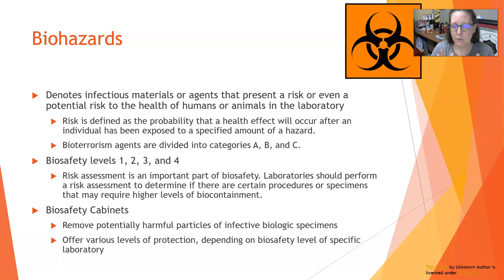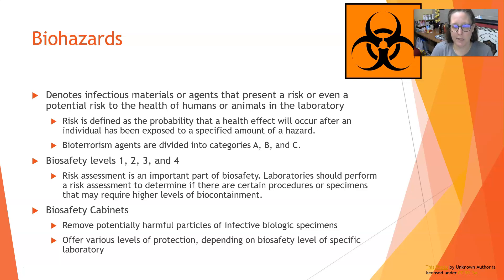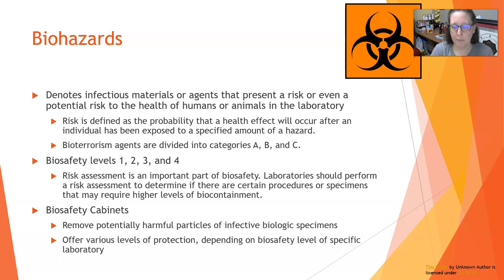Most hospital and clinic labs are going to be biosafety level two. To contain biohazards, labs use biosafety cabinets and biosafety hoods, which are designed to remove potentially harmful particles or infective biological specimens. They offer various levels of protection depending on the biosafety level needed, and are designed with specific airflow so that anything that becomes airborne is drawn into the airstream away from the worker.